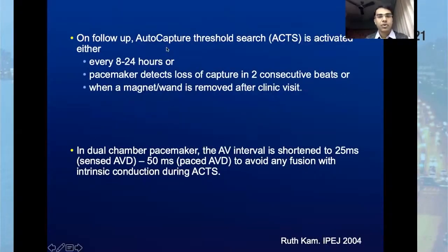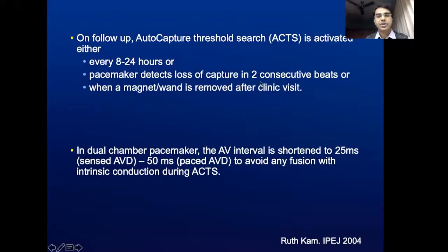On follow-up, when does the auto capture threshold search happen? Like in this case, we feel that there's auto capture threshold search going on. Either it happens every 8 to 24 hours, which can be preset, or if the pacemaker detects loss of capture in 2 consecutive beats and there is a backup pulse, then it can start an auto capture threshold search, thinking that there might be some threshold issue. The third scenario is when a patient leaves a device clinic after the device checkup or wand removal or magnet removal. This auto capture threshold search happens once again.